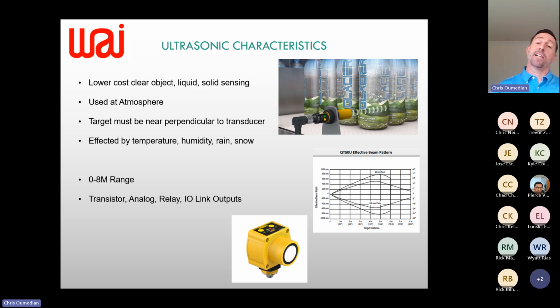If you refer back to the diagram of shooting that signal out, measuring the time and coming back, imagine if you do a billiard shot off the side of the tank and off the bottom and back - you're going to get a super weird value. So just another thing to be aware of: that effective beam pattern, and making sure you've got a robust solution for the application.